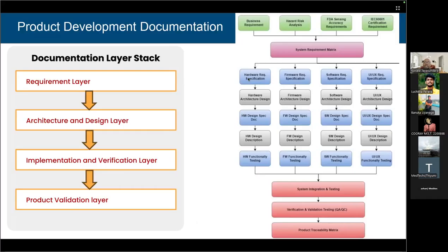And then you can write down the specifications for the hardware development, firmware development, software development, UI UX development, everything. So for an example, the alarms, on time, off time, decibel levels are given in UI UX requirement. And if there's a doctor's portal, then the doctor's portal's individual buttons have their own specific colors that you can't change.